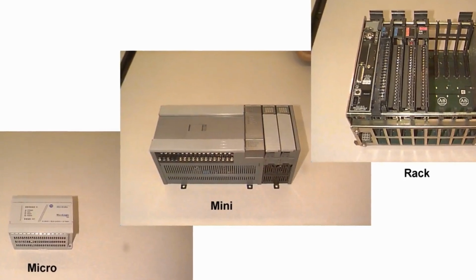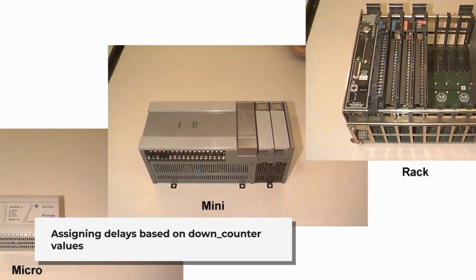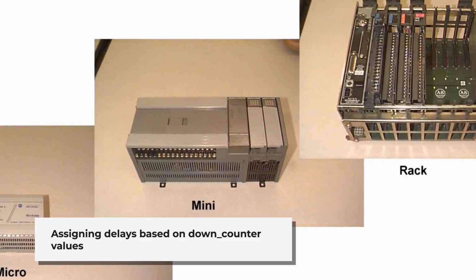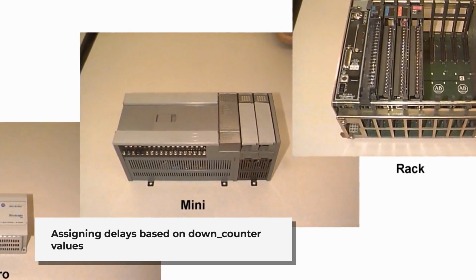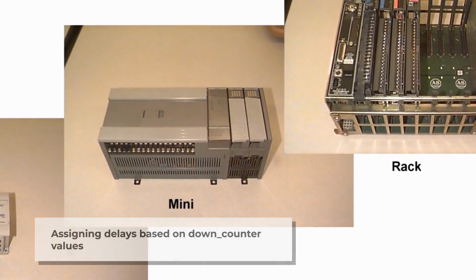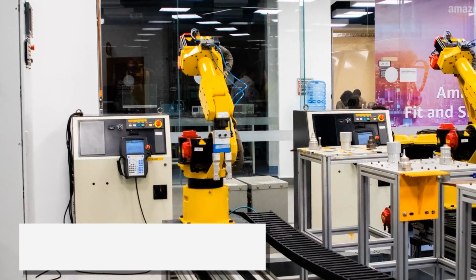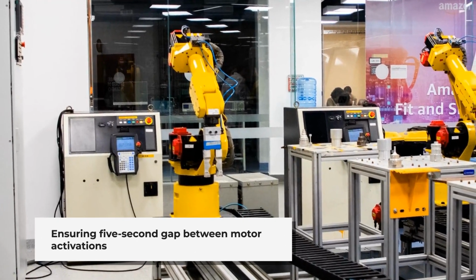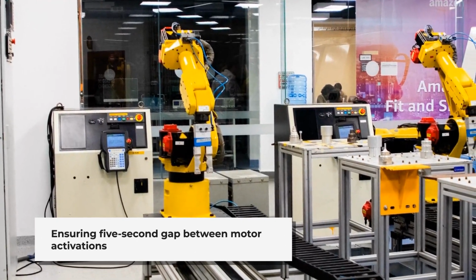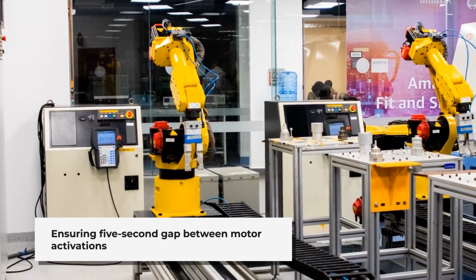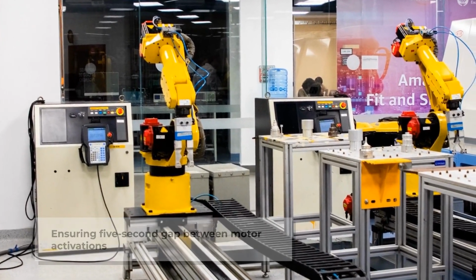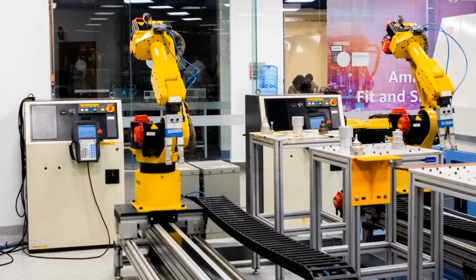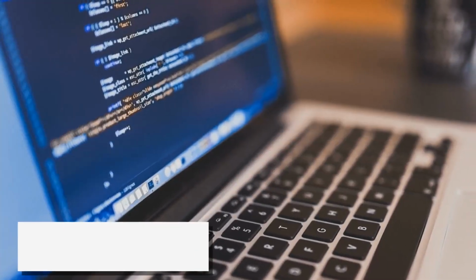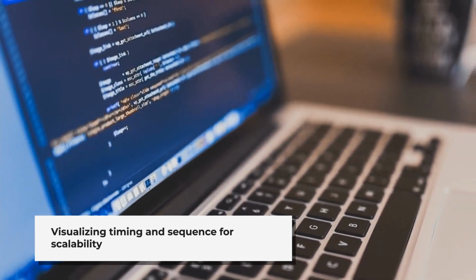Let's say you want to start motor 4. You would take the current value of the down counter, assign it to on delay 4, and then add 5 seconds to the down counter. If motor 4 is the first, it starts immediately since the down counter is at 0. If another motor is started shortly after, its delay is set based on the down counter's current value, ensuring a 5-second gap. By mapping this out in a spreadsheet, you can visualize the timing and sequence.